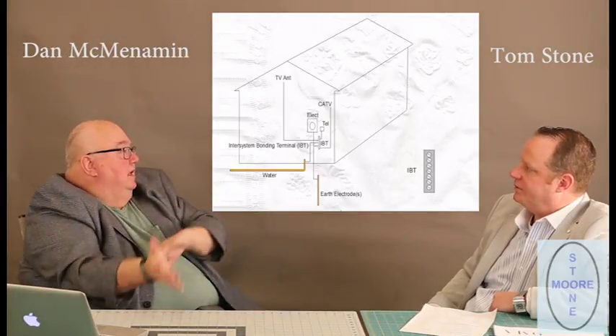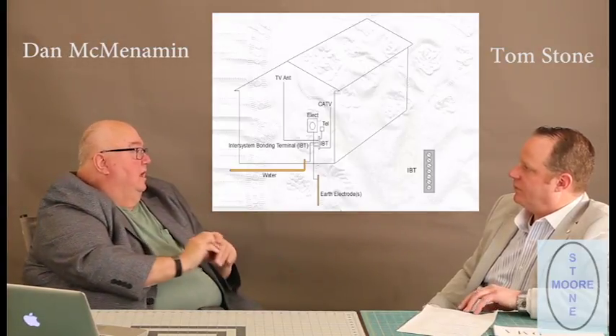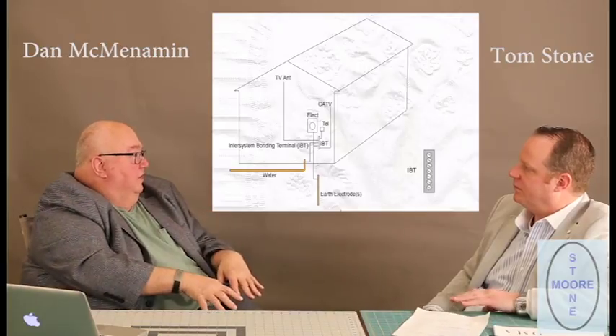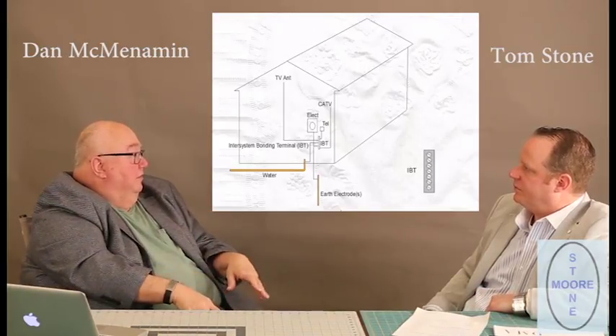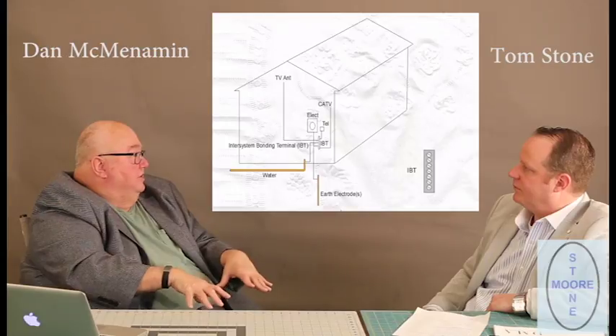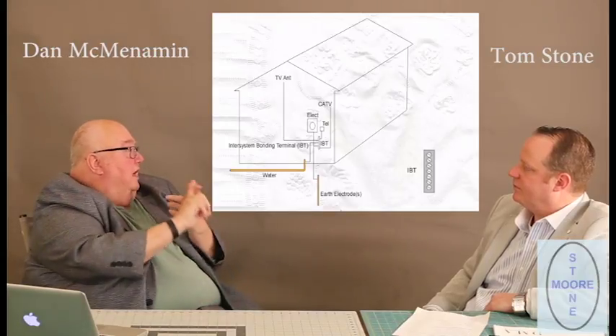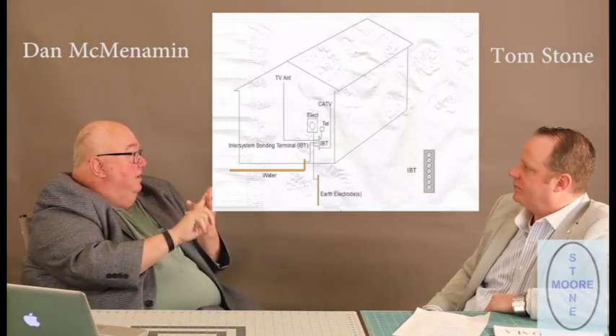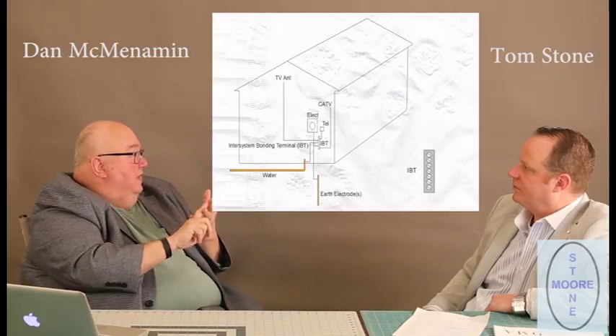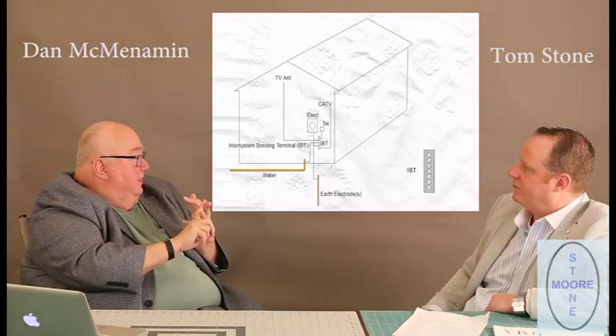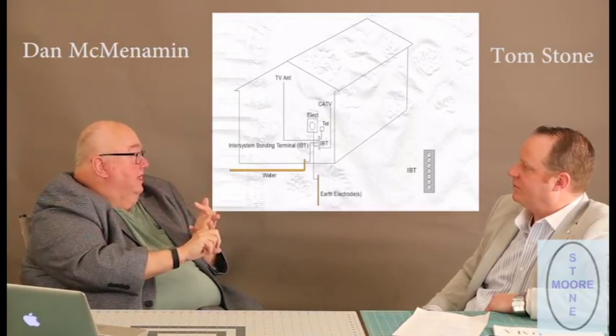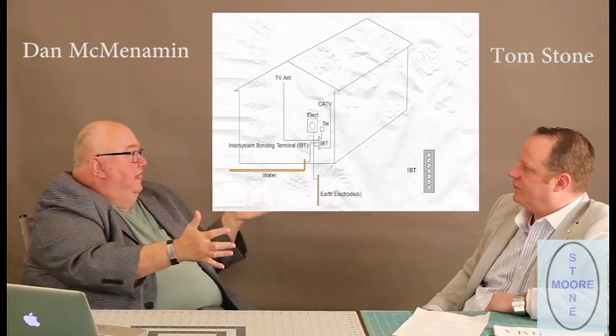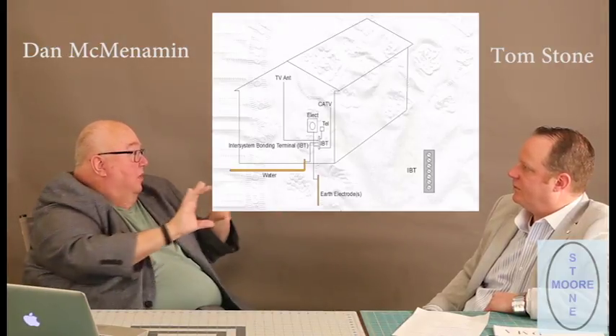All right, now let's go into the central office. We've got earthing electrodes in there. They're driven ground rods out there in various configurations that are used. And then you've got electric coming in, the house service board. You've got maybe a metallic building that could be a lightning target, or you've got lightning rods, all that stuff. All those things tie together on that bar. So that bar just becomes a big inter-system bonding terminal.